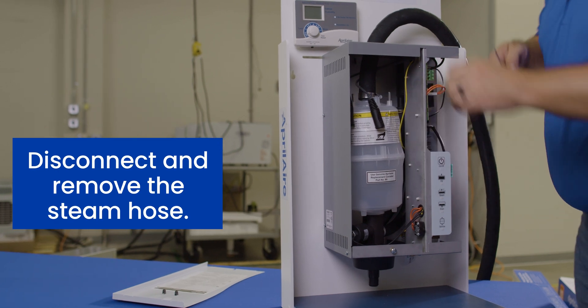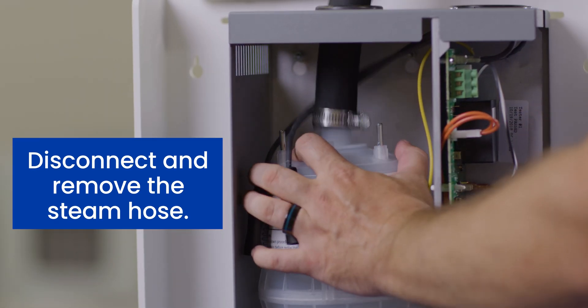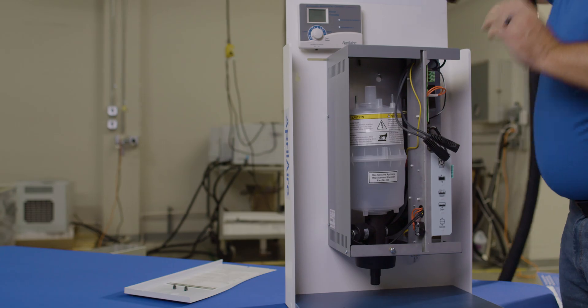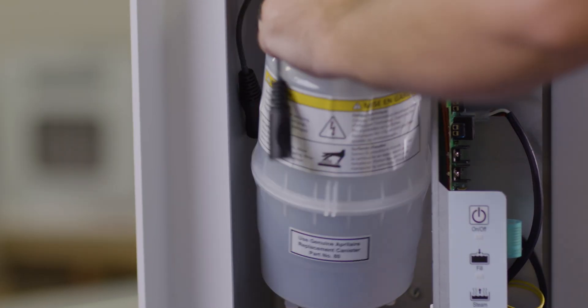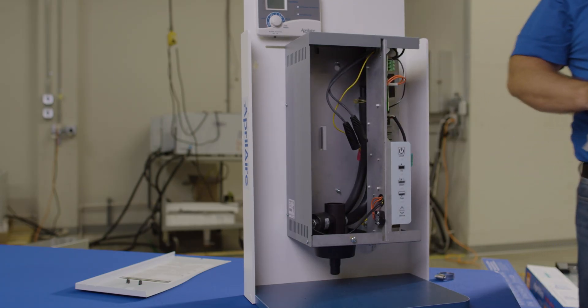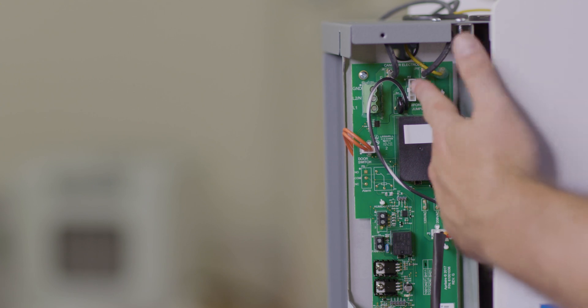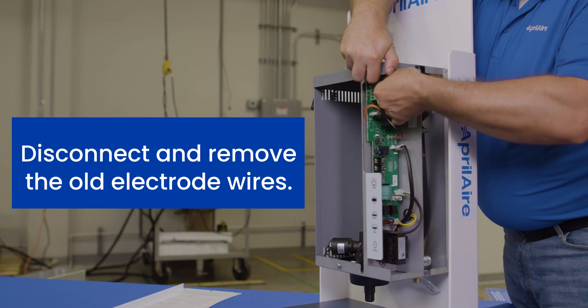Loosen the hose clamp at the top of the canister and slide the steam hose off. With everything disconnected, you can now remove and discard the old canister. Disconnect the electrode wires from the printed circuit board and then discard them.